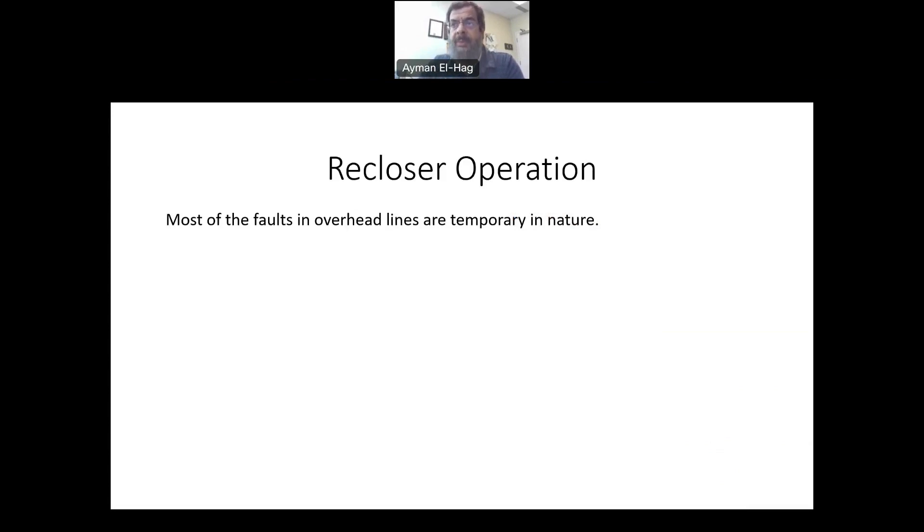This is why when we have such a fault which is temporary in nature, we don't want to have a system that opens the circuit permanently. We want to have a protection system that temporarily clears the fault and tries to re-energize the system again to check if the fault has been cleared or not. And that is basically the main functionality of the Recloser.